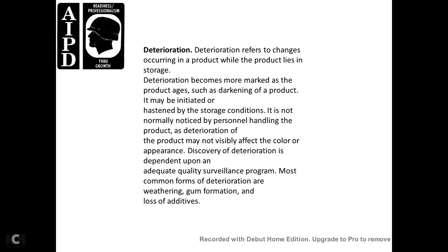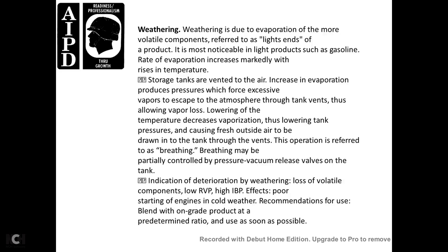Deterioration may not be visible in effective color appearance. Adequate quality surveillance is needed to discover deterioration. The most common forms of deterioration are weathering, gum formation, and loss of additives. Weathering is due to evaporation of the more volatile components (light ends) of the product; it is most noticeable with light products such as gasoline. The rate of evaporation increases markedly with a rise in temperature.